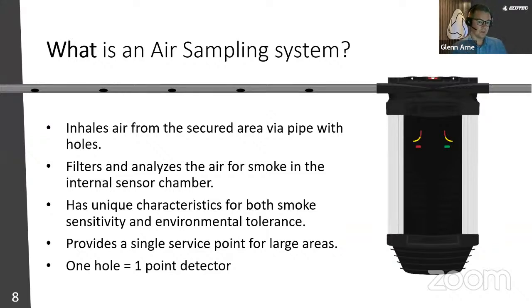So I think we are going to start a little basic. What is an air sampling system? The air sampling system is a unit that inhales the air from the secured area via a pipe with holes. It filters and analyzes the air for smoke in the internal sensor chamber, has unique characteristics for both smoke sensitivity and environmental tolerance. And it also provides a single service point for large areas, which makes it much easier to do service and commissioning. And one thing we have to remember is that one hole on the pipe is the same as one point detector.